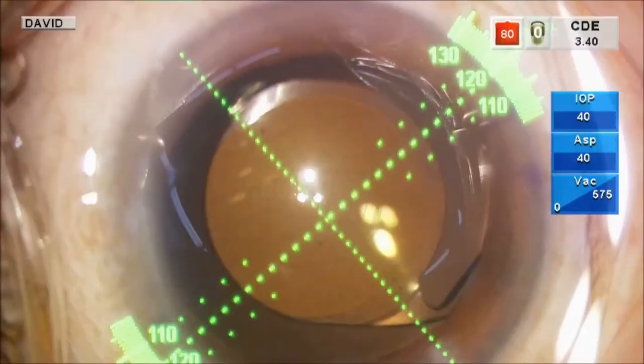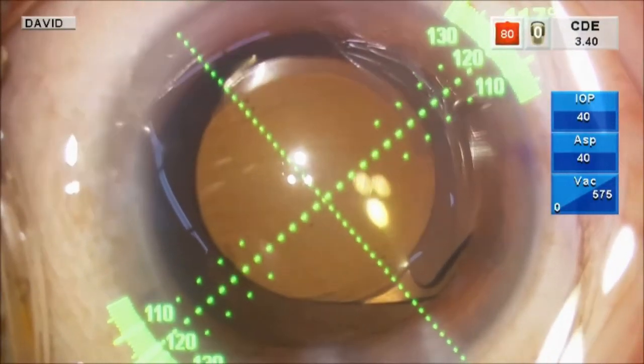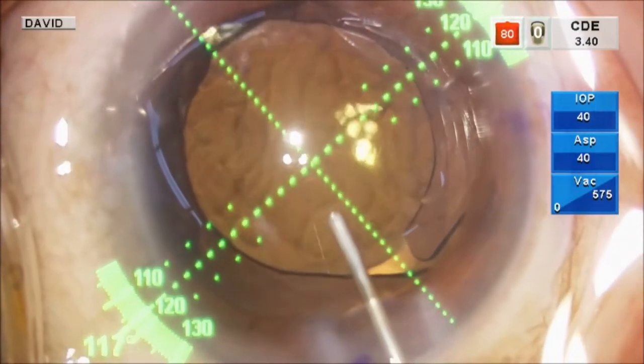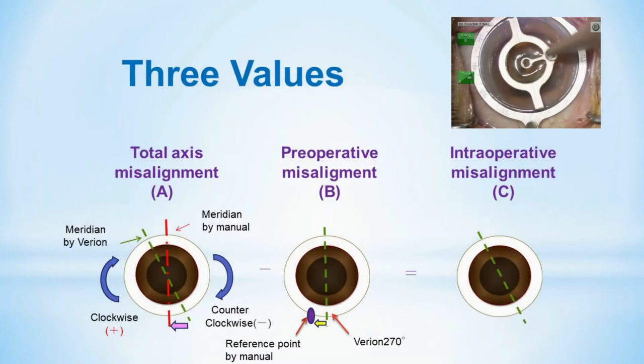These two meridian differences were measured. In this case, there is an 11-degree misalignment. We measured three misalignment values between two methods in the same eye. Total axis misalignment is a discrepancy of the intended steep meridian between two methods. Preoperative misalignment is a discrepancy of the 6 o'clock reference point by manual method and 270 degrees by image-guided system. Intraoperative misalignment is the value of total misalignment subtracted by preoperative misalignment.